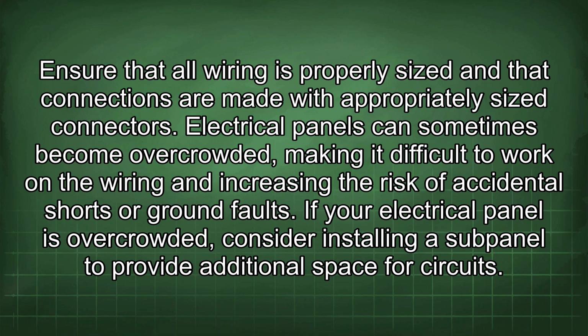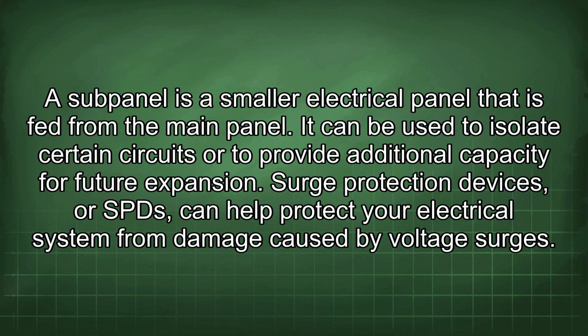Electrical panels can sometimes become overcrowded, making it difficult to work on the wiring and increasing the risk of accidental shorts or ground faults. If your electrical panel is overcrowded, consider installing a subpanel to provide additional space for circuits. A subpanel is a smaller electrical panel that is fed from the main panel. It can be used to isolate certain circuits or to provide additional capacity for future expansion.